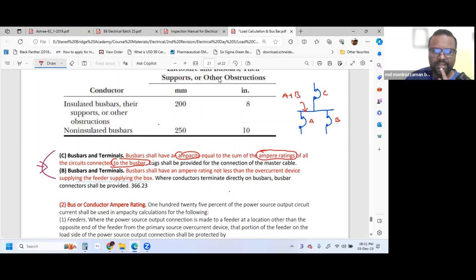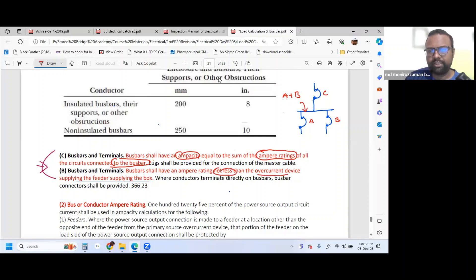Bus bar is the Terminal. Bus bar shall have an Ampere Rating not less than the overcurrent device connecting the feeder supplying the box. The Bus bar Ampere Rating shall be not less than the overcurrent device. The overcurrent device is the circuit breaker or fuse.